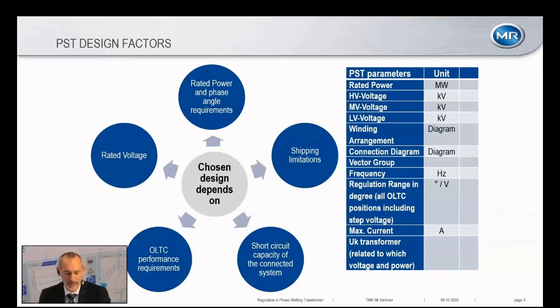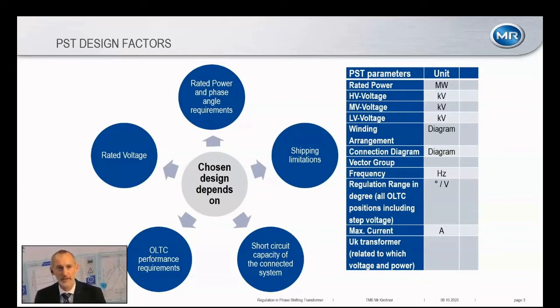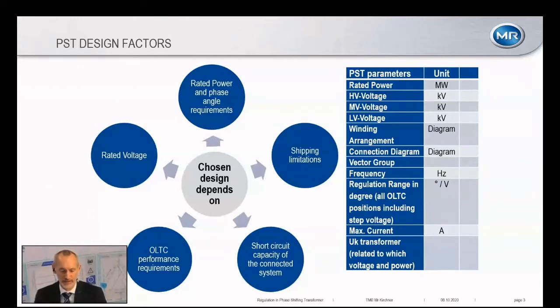OLTC performance requirements are a key point for phase shifting transformers. For OEMs new to this business, it's a different situation: with a normal transformer, you create a design, select an OLTC, and everything is fine. With phase shifting transformers, the limiting component is often the on-load tap changer. If that's the case, you must start with the capability of the on-load tap changer and then adapt your transformer design accordingly to get the most out of your PST.